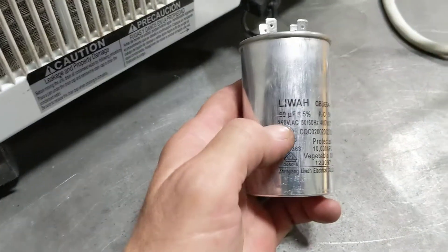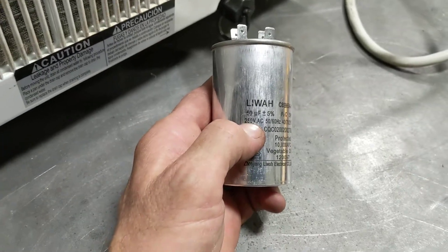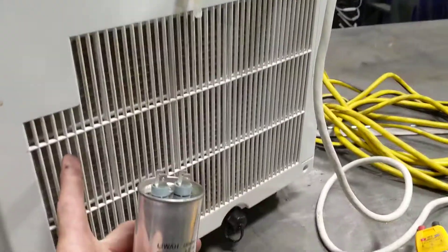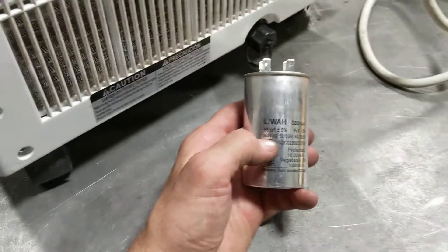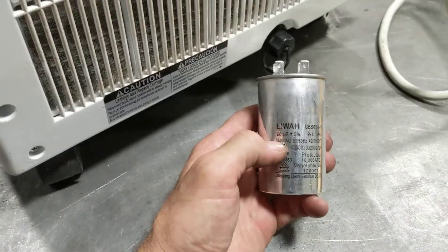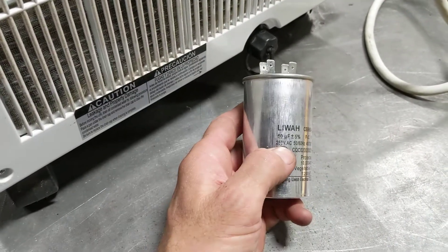You don't have to buy the manufacturer's capacitor — that might be 3-4 times the price. You can get a universal capacitor, as long as you have this voltage — that it's that voltage or higher. This one here is a 60 microfarad, 250 volt AC. Now this is a 125 volt system. What it's saying is that capacitor has a 250 volt AC rating — it just means that's how heavy duty it is. The one I put in there was a 440 VAC, so it's going to be a lot heavier duty than this. It was a bit longer, but it still fit.